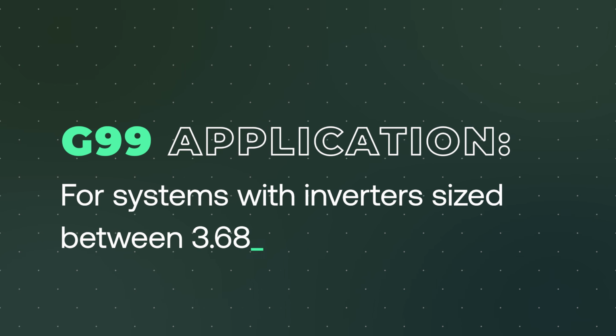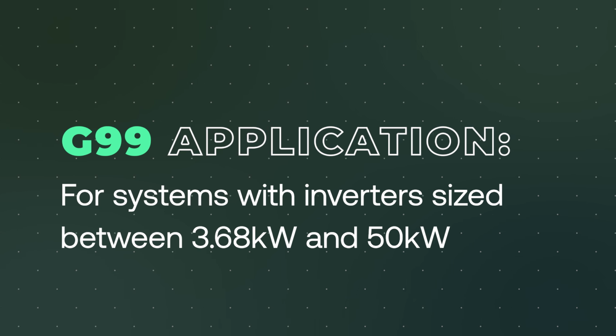Now 3.68 kilowatts up to 50, most domestic suppliers can't take a 50, that's small scale commercial, is covered by a G99 application. That's what the network operator wants to know, the size of the inverter, because that's the theoretical limit flow rate of electricity at any point in time they could receive onto their grid. They're not too concerned with how many kilowatt hours we export over the course of the year. What they care about is, at a point in time, what's the most that this inverter can send out to the grid.